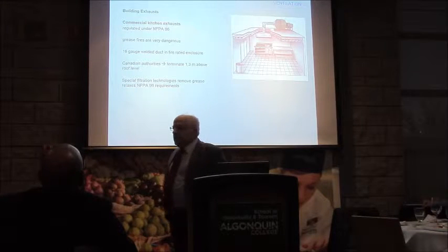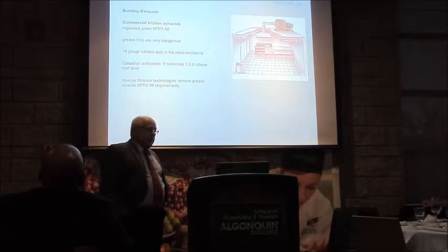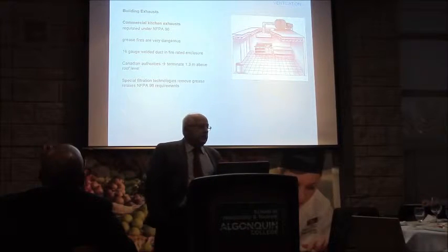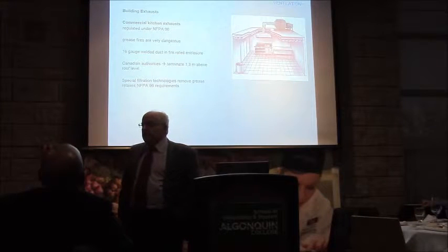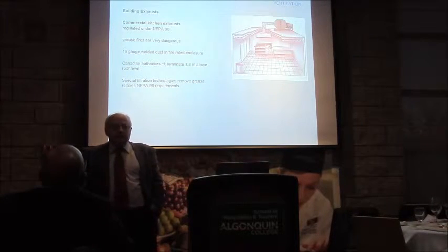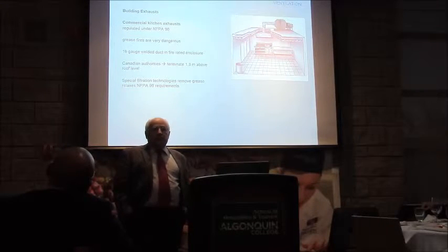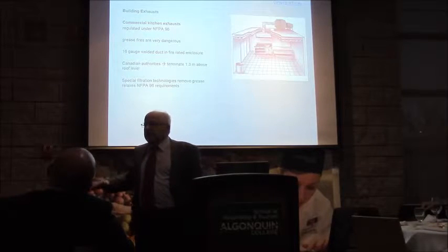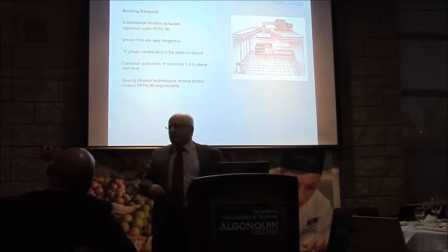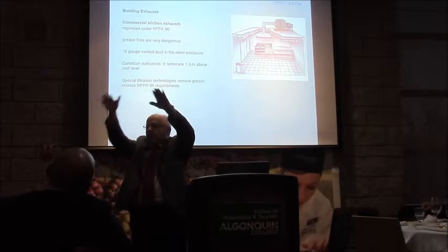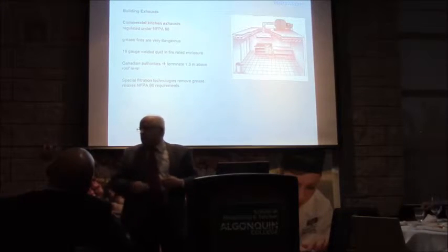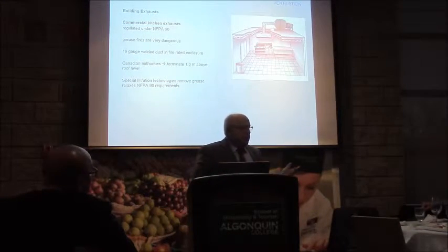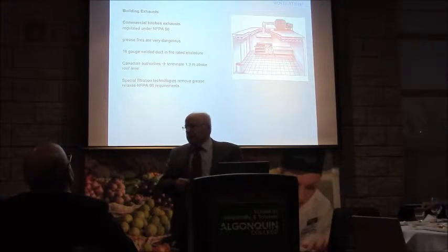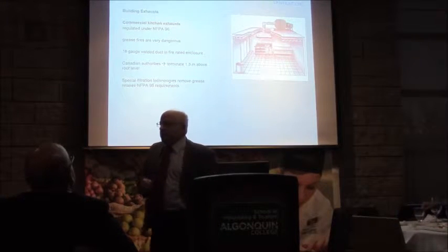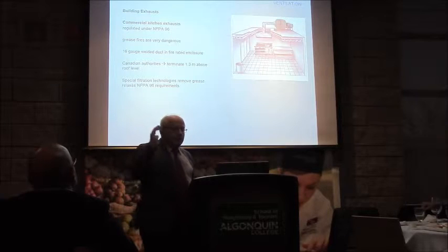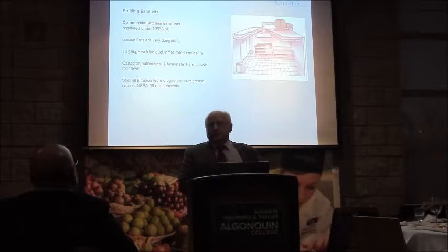Kitchen exhausts in a tall building are a challenge. Sometimes there are setbacks that give us roof space, but I would suggest it's not a particularly happy owner who wishes to see our kind of junk on a ceiling visible from everybody above the fourth floor, let's say, in a building. So if you've got a building that's stepping back, everybody can look down on that roof, and they don't really want to see all the kind of stuff that we would have. So having a miscellaneous kitchen exhaust fan around is not on. We'll have grease extraction, some kind of ecologizer type system, and collect that together and take it out the side, in a much less obtrusive place.